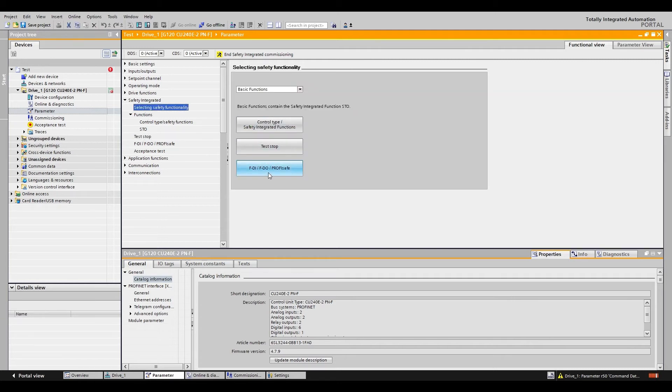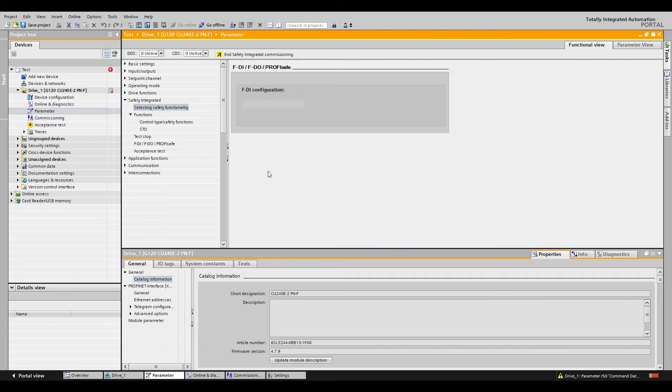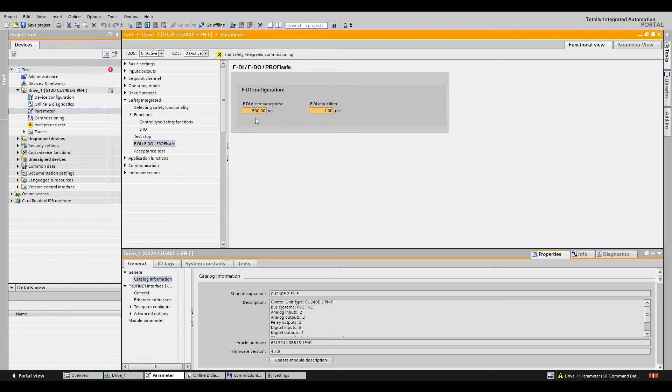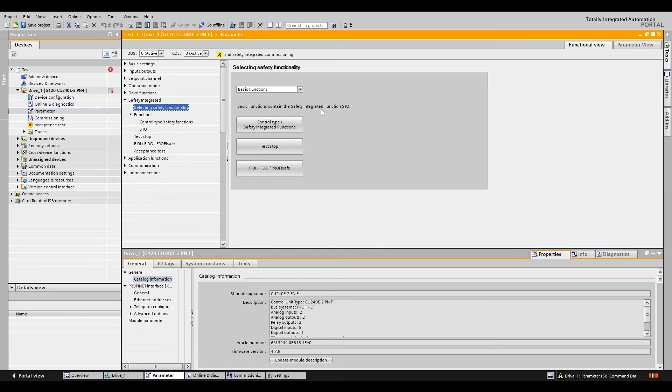And the last button is the discrepancy time which is the time window that the two input channels need to change in and then the input filter which is a debounce time. And that is all the settings for the G120 basic functions.